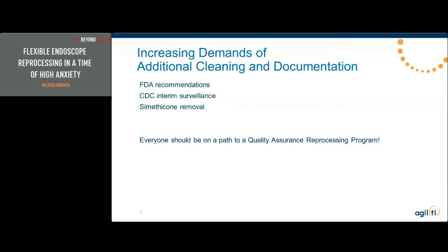There were numerous notifications specific to reprocessing duodenoscopes through this time, and many facilities still run their HLD process twice. A select few who still have access to EO sterilization have incorporated that. Culturing per the CDC's interim surveillance instruction is still recommended, and post-market surveillance study is ongoing, although right now the results have not been terribly encouraging regarding contamination rates.